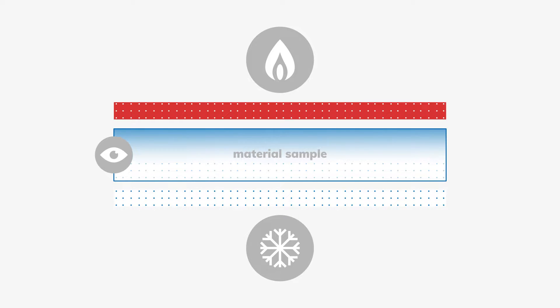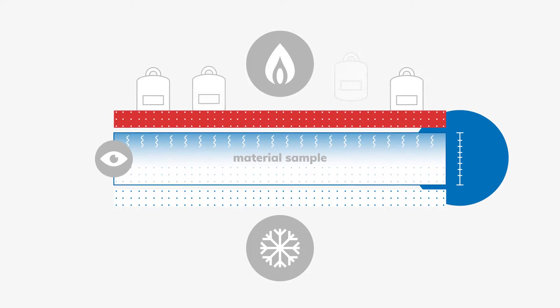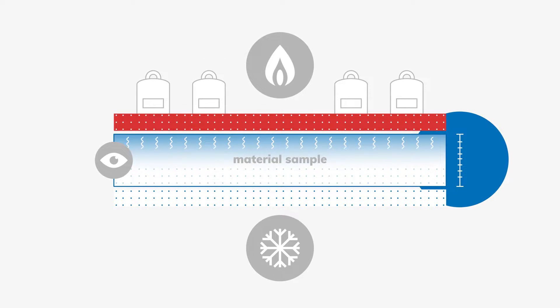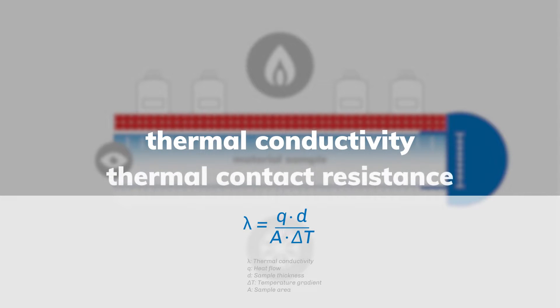Knowing the sample thickness and the measured heat flux, the sample's thermal conductivity can be calculated. With the TIM tester, the thermal resistance under variable load or compression can be measured, and from this, the thermal conductivity and the thermal contact resistance can be determined.